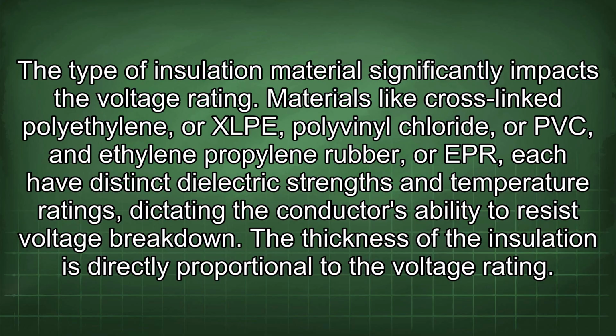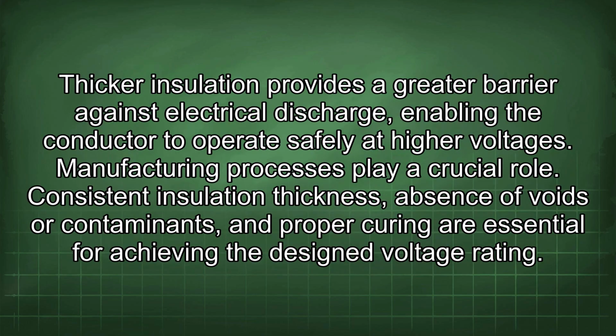The thickness of the insulation is directly proportional to the voltage rating. Thicker insulation provides a greater barrier against electrical discharge, enabling the conductor to operate safely at higher voltages. Manufacturing processes play a crucial role. Consistent insulation thickness, absence of voids or contaminants, and proper curing are essential for achieving the desired voltage rating.